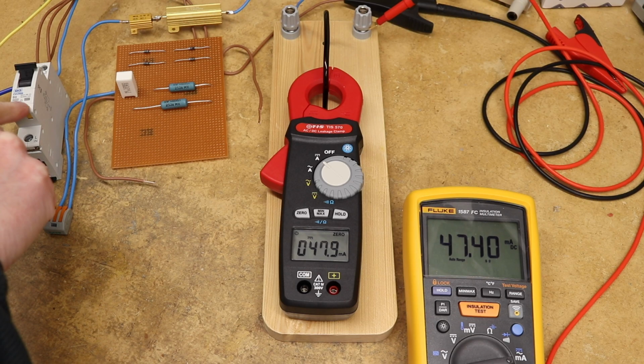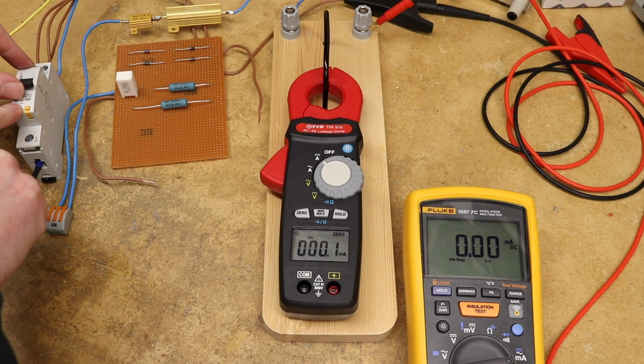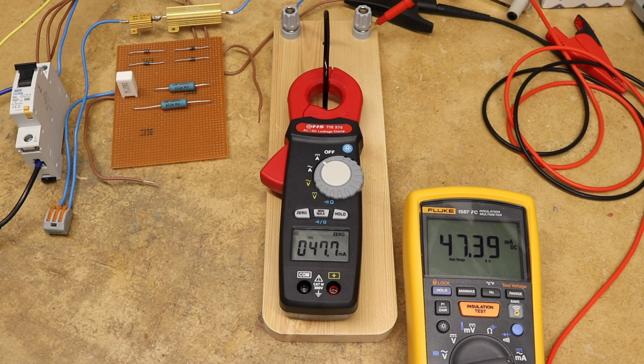I haven't managed to trip this one. It's still not tripping even with a tester on there, so perhaps I haven't got enough DC current going into it to do that. That's the reason why you check for DC current within the UK, where AC RCDs and RCBOs are still fairly commonplace, although they're slowly being replaced with Type A, especially since the change in Amendment 2 of the regs.